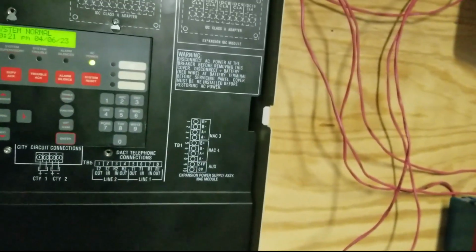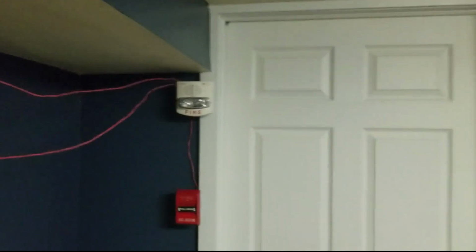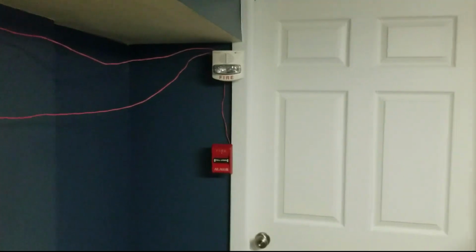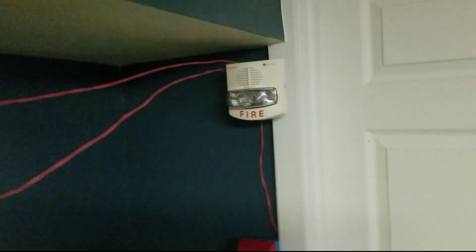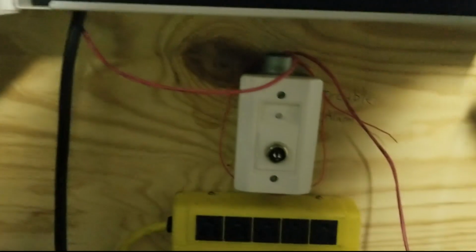What I decided to do instead is, for this one time, I have the horn on that enabled. It is set to temporal. I better grab my ear protection real quick. Yes, so this horn is now enabled. It'll be doing temporal, and we are going to activate it with the fire drill switch.